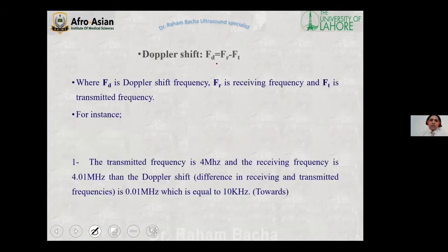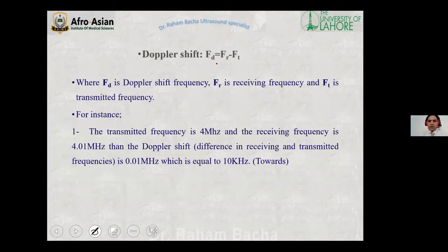For example, your transducer is operating at a frequency of 4 megahertz, and the receiving frequency is 4.01 megahertz. According to this formula, the difference between the receiving and transmitted frequency is 0.01 megahertz, which is equal to 10 kilohertz. So this 10 kilohertz is the Doppler shift. The reflector is moving towards the transducer, because this Doppler shift is positive, meaning the receiving frequency is higher than the transmitted frequency.